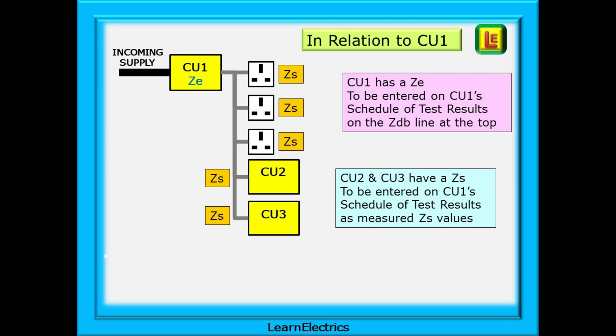In relation to CU1 certificates and test schedule, what have we got here? We have a consumer unit with the incoming supply going to it. We measure the earth fault loop impedance at the main switch and this is ZE. It is entered as ZE on the certificate supply details and as ZDB on the schedule of test results. CU2 and CU3 will have the loop impedance measured at their own main switches and these will be recorded as ZS values on CU1's schedule of test results.